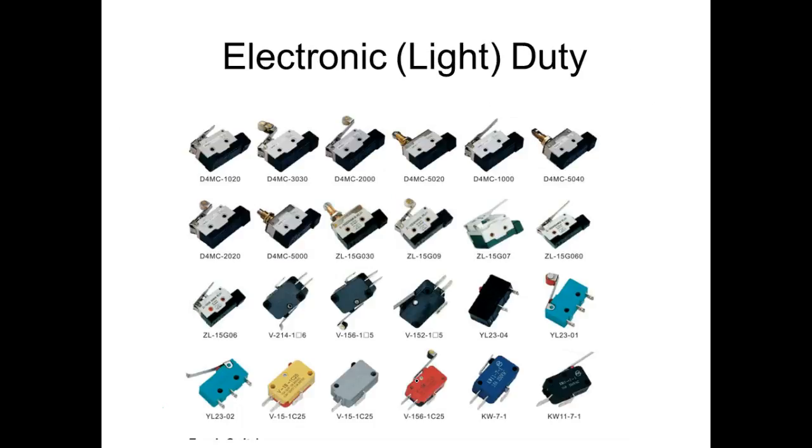This is electronic duty. These guys are really, really small. Usually you buy it with the type of actuator that you want. So this would be a roller, this is just a plunger type. They all activate just about the same way. These are going to be really small. They do not handle a lot of current. An input into a PLC doesn't hardly need any current at all. We could look up the data sheets for a PLC and see how much current is required by the input, but it's usually very low.